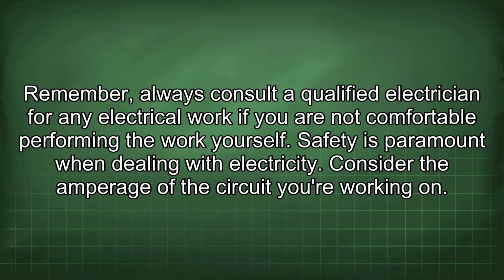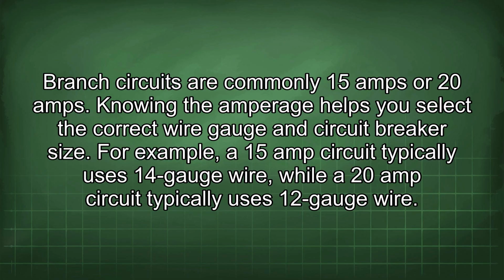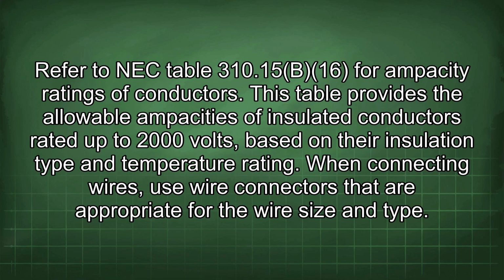Consider the amperage of the circuit you're working on. Branch circuits are commonly 15 amps or 20 amps. Knowing the amperage helps you select the correct wire gauge and circuit breaker size. For example, a 15 amp circuit typically uses 14 gauge wire, while a 20 amp circuit typically uses 12 gauge wire.